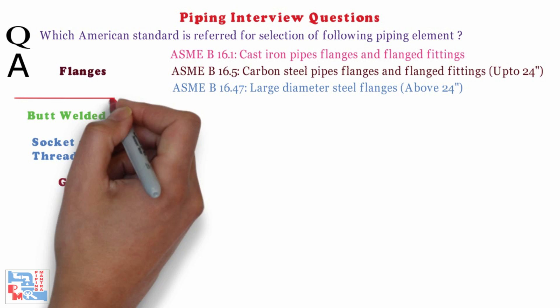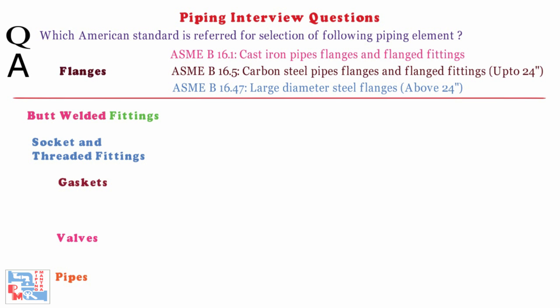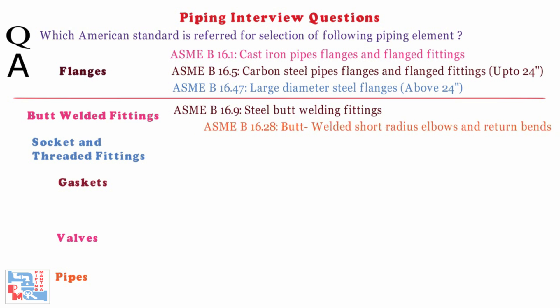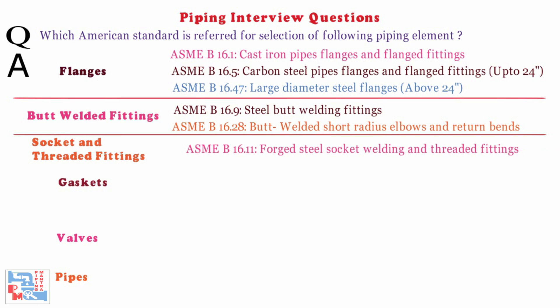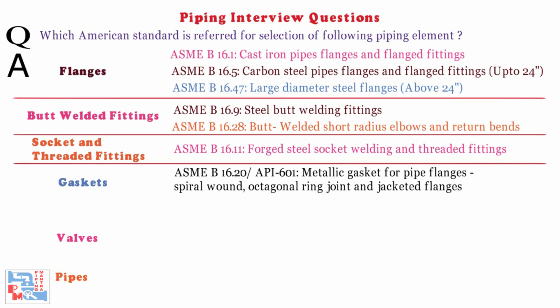For butt welded fittings: ASME B16.9 is used for steel butt welded fittings. ASME B16.28 is for butt welded short radius elbows and return bends. For socket and threaded fittings: ASME B16.11 is used for forged steel socket welded and threaded fittings. For gaskets: ASME B16.20 or API 601 is used for metallic gaskets for pipe flanges, including spiral wound, octagonal ring joint, and jacketed flanges.